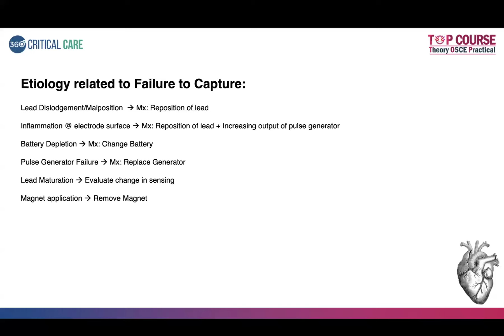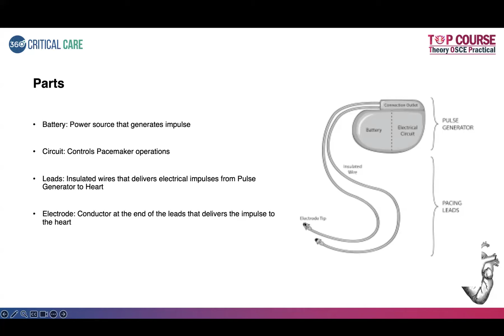If you know the structure of a permanent pacemaker, you will be able to understand the complications, or the areas where problems can occur because of failure to capture. All right. You can see it in the previous diagram. The parts are the battery and the electrical circuit. These two together are called the pulse generator. If there is any issue over here, you'll need to replace that. If there is an issue in the battery, you need to change it. If there is a magnet placed over the circuit, then you will have to remove the magnet. If the electrode tip is eroding or there is inflammation, then you'll have to increase the output. And if the wires are malpositioned, then you'll have to reposition them.